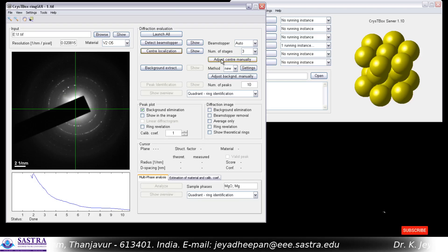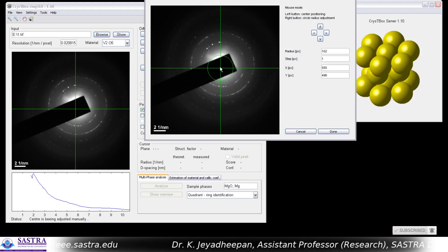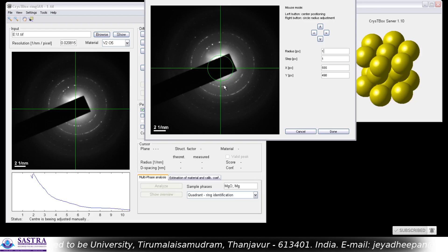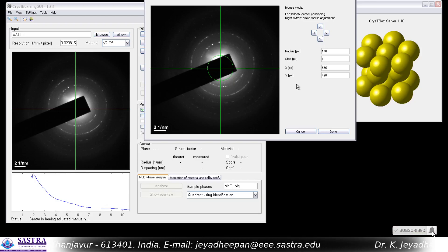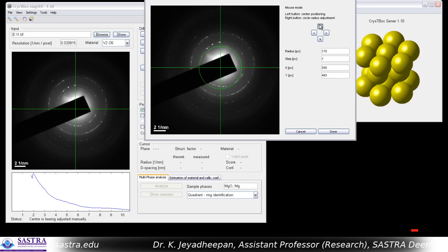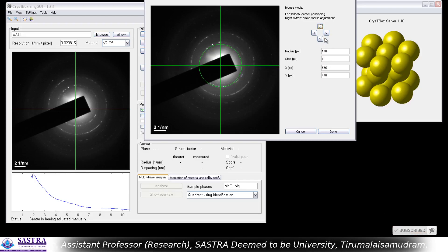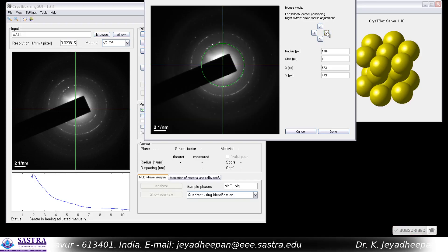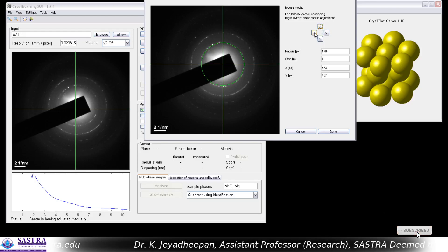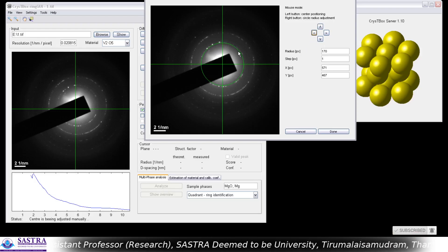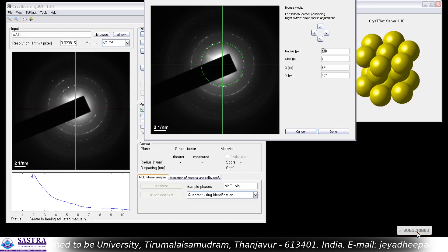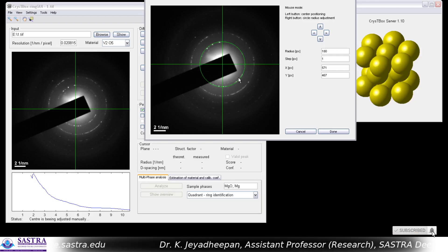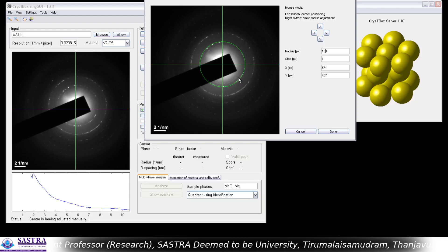So I am going to adjust the center manually. You can clearly see the center is not at the ring centers. I am increasing the radius of the green ring to about 170, then pressing Enter. I am going to adjust the center using the up, down, left, and right arrow keys. Now you can see the center point is somewhat fixed correctly. Increasing the radius to 180, you can see the first ring and the green ring are matching exactly to each other. This is how you can exactly fix the center of the rings.